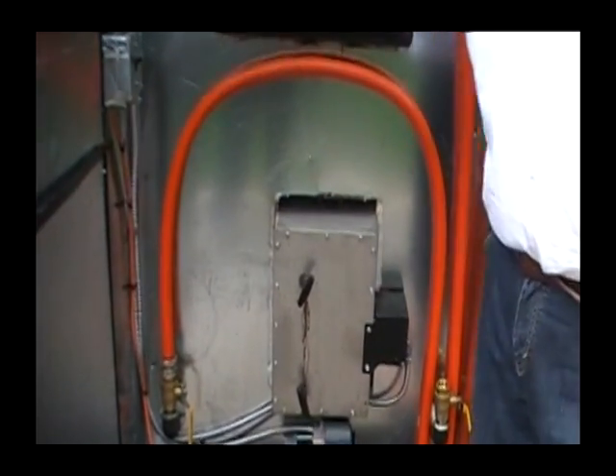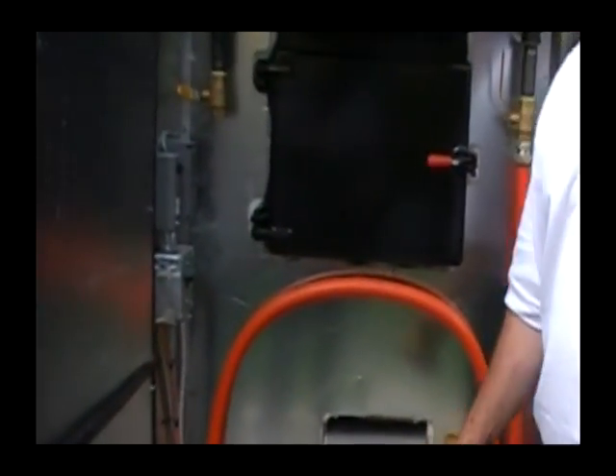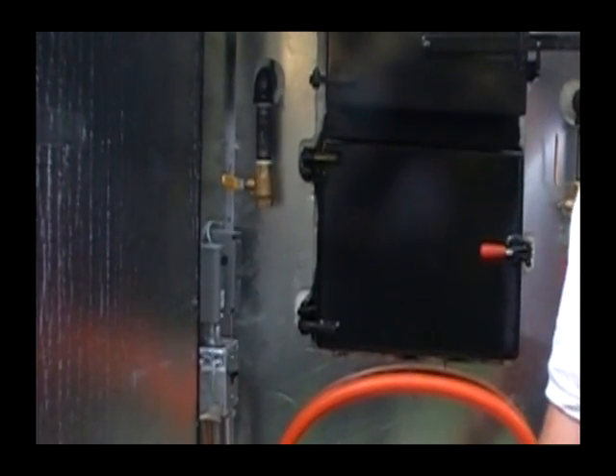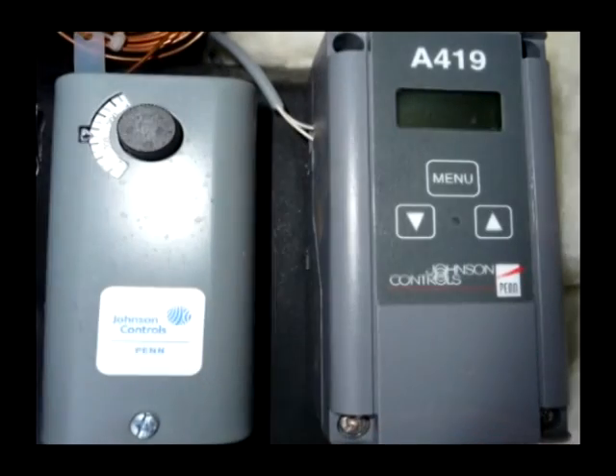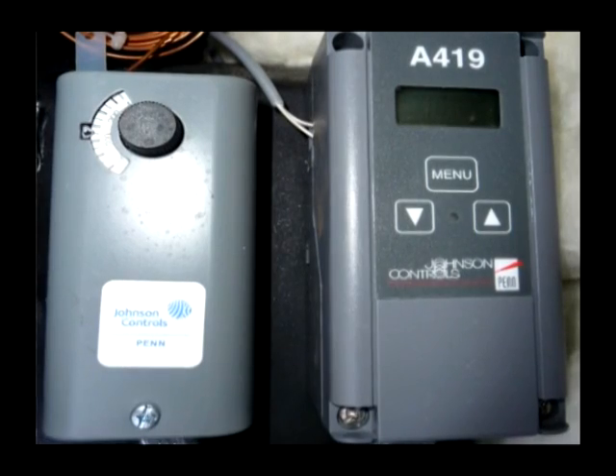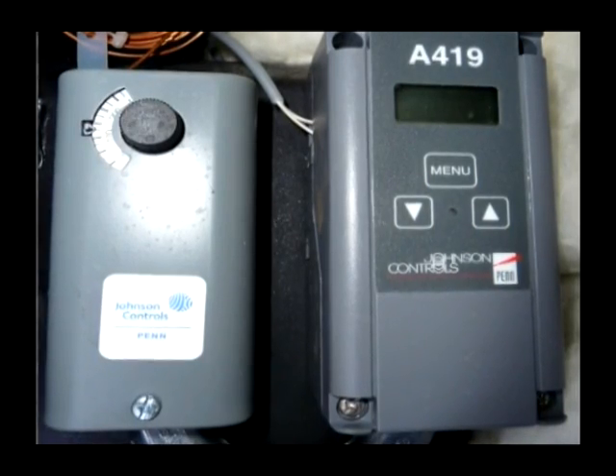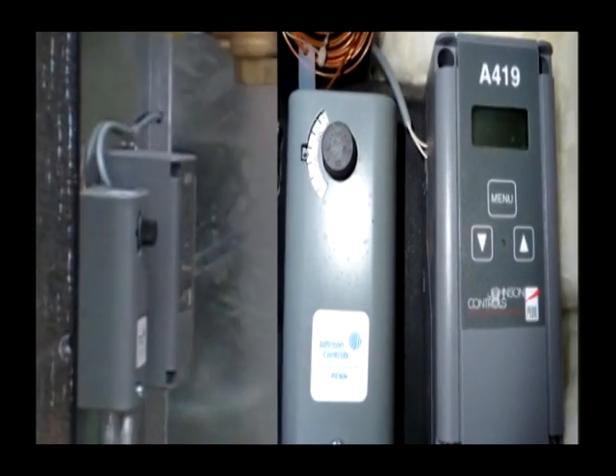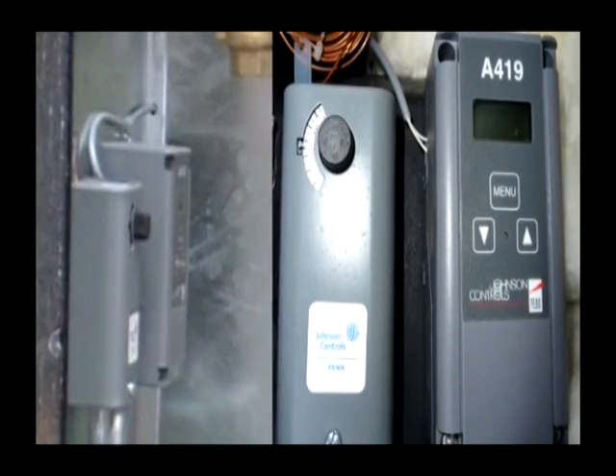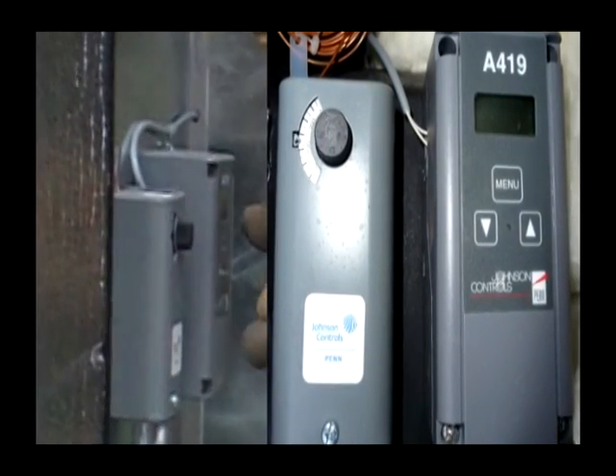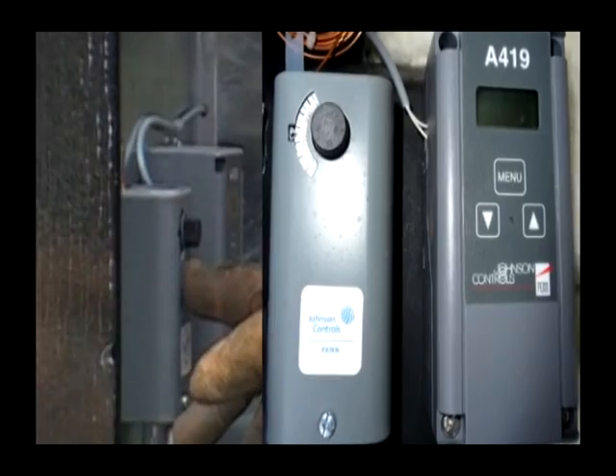Johnson Control A419 Aquastat, accurate within 1 degree. You can set your differential in there, up to 30-degree differential. High limit for safety. The high limit will shut everything down before it got to a boiling point. Johnson Control off-the-shelf Aquastats, very easy to get. Will last for a long time inside the cabinet, out of the weather, out of the smoke.